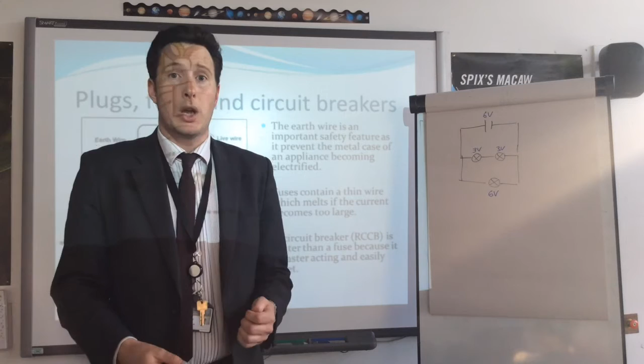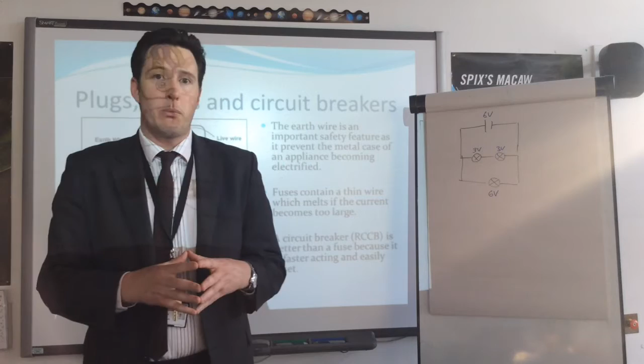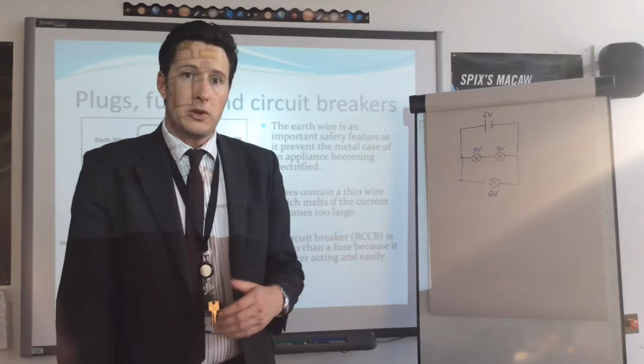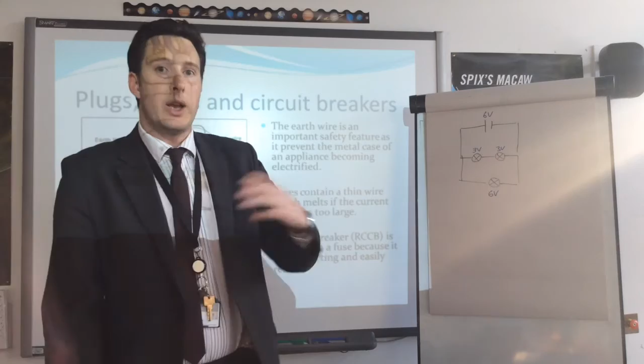Another example could be if I had an appliance that had a current of 4.5 amps, I would use the 5 amp fuse because it's above the current I need to sustain, but I could not use the 3 amp fuse because it would be too low and it would melt even when the appliance was working perfectly. I wouldn't go up to the 13 amp fuse because that would be too large a jump, and if that appliance had a fault it would not melt and cut off.